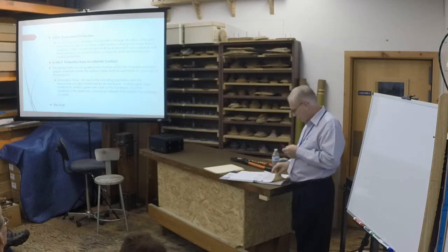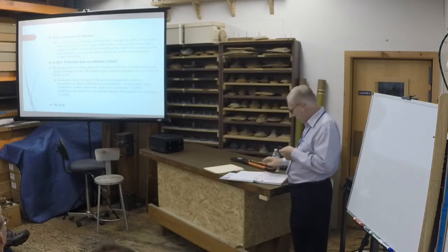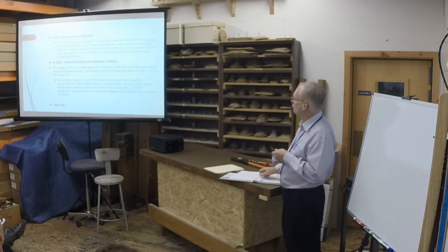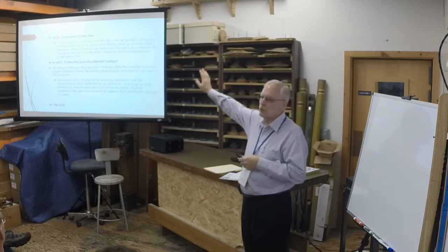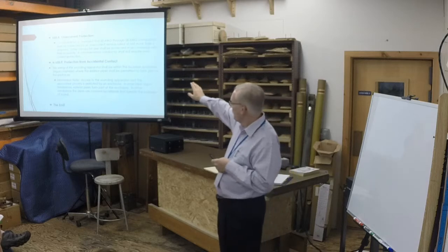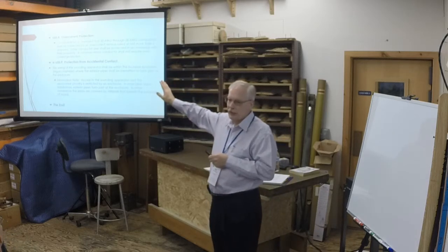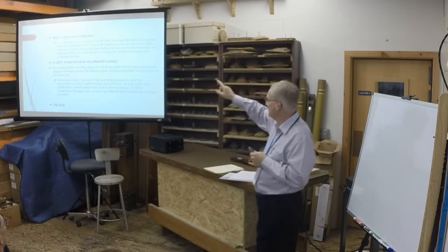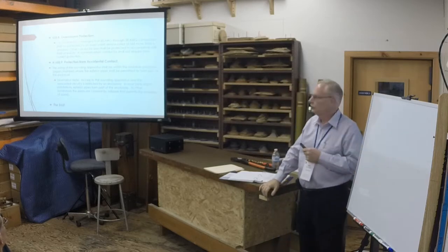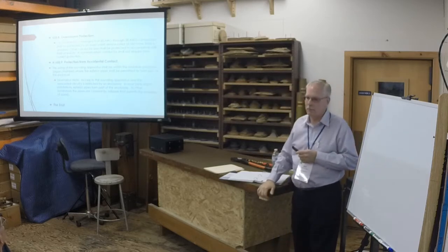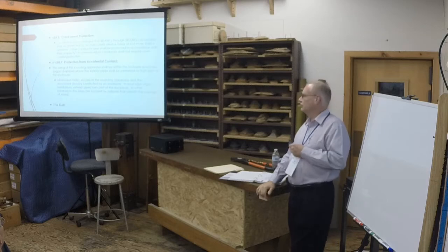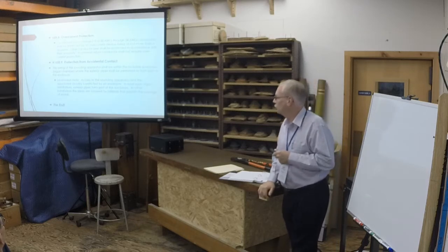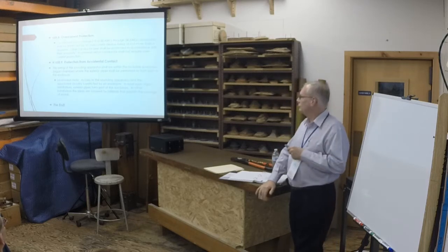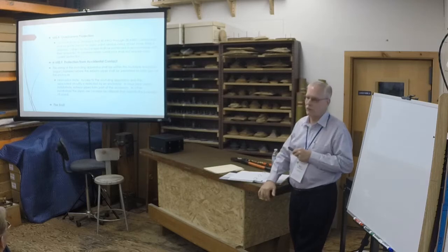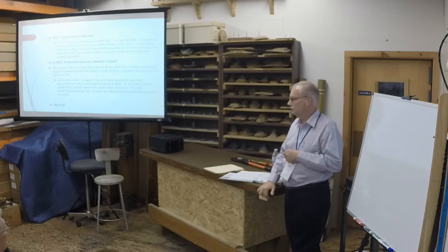Overcurrent protection. Here comes the biggie - a major change, and I have that in red for a reason. Up till this change in 2017, the code previously read 24 gauge and up. It is now 20 gauge through 28, stipulating that anything even smaller than 28 is no longer acceptable.